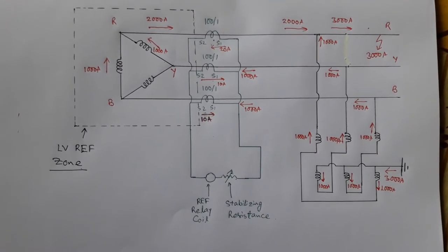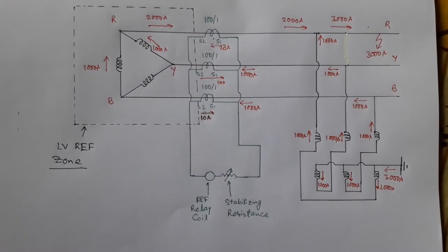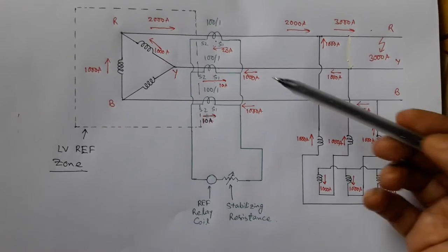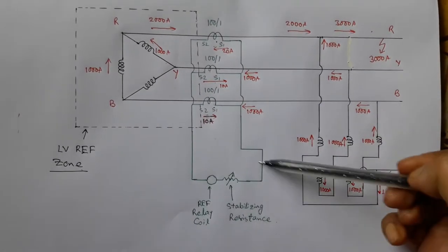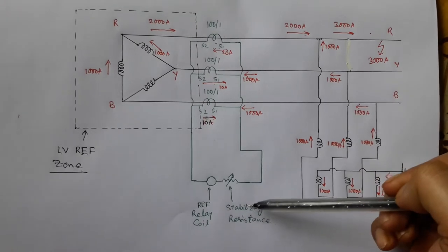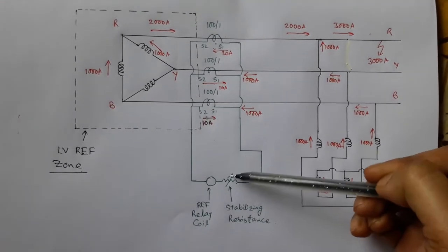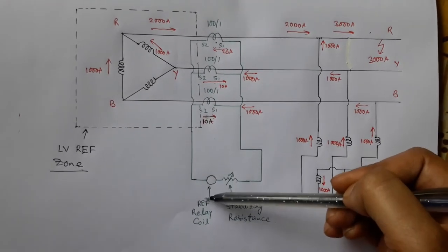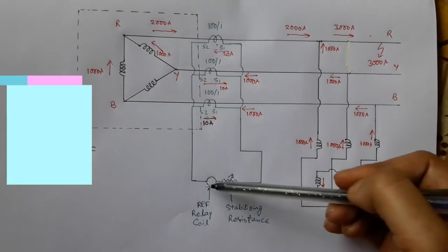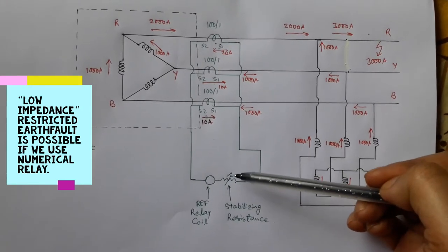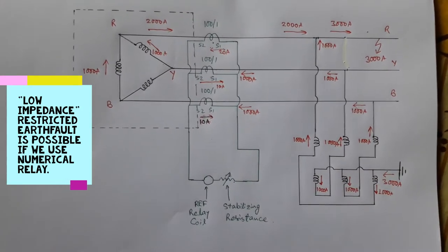In this example we are discussing a traditional restricted earth fault relay. In this restricted earth fault protection, a high value of stabilizing resistance is connected in series with the REF coil. That is why this type of protection is also called high impedance restricted earth fault relay.